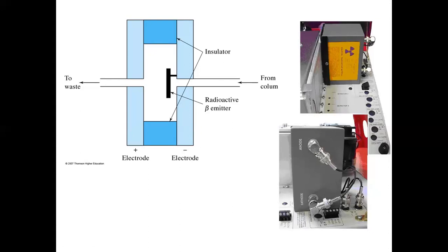So solutes are separated out from the chromatographic column. The solutes coming out from the chromatographic column are going to capture the electrons present in this flow here. This is called electron capturing by the solute. As a result of this electron capturing, the current is going to drift from its original value. This is going to be proportional to the amount of the solute or the nature of the solute, right? So this is how the beta ray emitter functions in the electron capture detector.